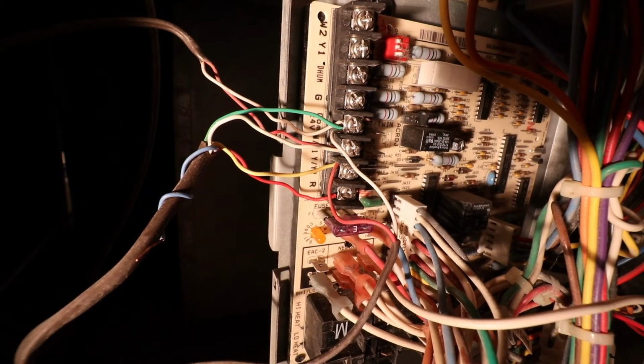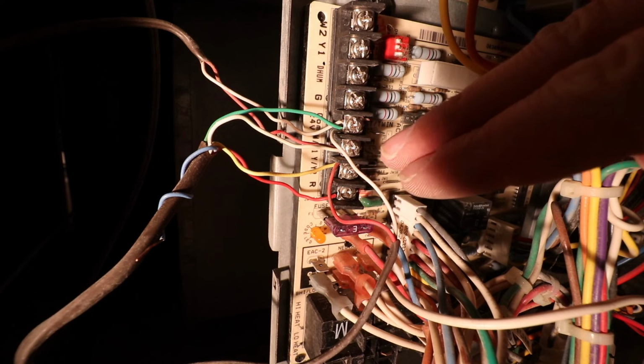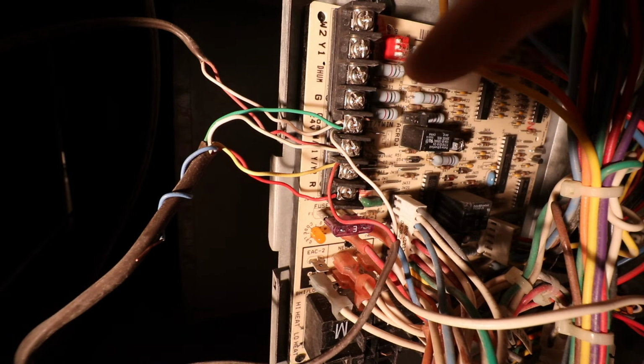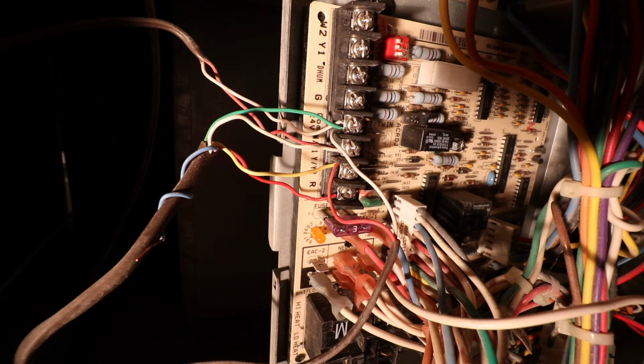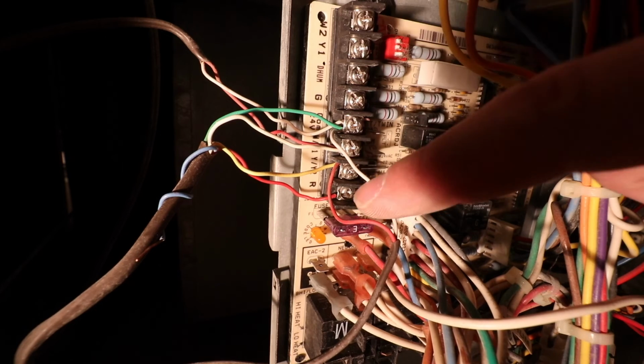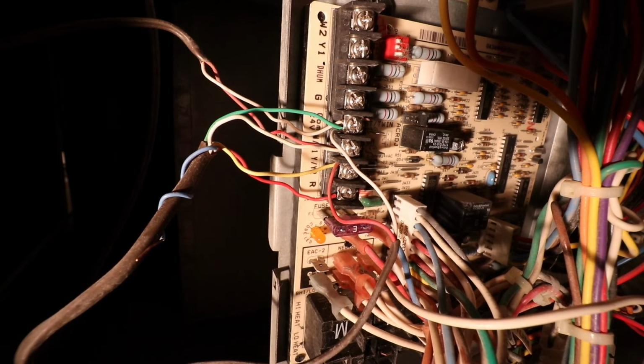It's important to leave those where they are on the circuit board. If they come off when you're moving that common wire around, go ahead and reinstall them where you had them. It's important to take a picture when you do this, so if any wiring gets changed around you can go back to that configuration. But leave these two wires alone, on the terminals they were on, and go ahead and get that G wire moved over to the C wire.